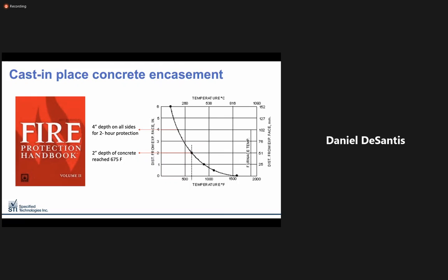This graph here, published by the NFPA in 2008, shows the temperature performance of cast-in-place concrete. This test was performed using an ASTM E119 time temperature curve for a typical cellulosic fire. As you'll see noted here, the unexposed side of 2-inch thick concrete reached 675 degrees Fahrenheit after just 2 hours, while 4 inches were required to maintain a passable temperature of about 325 degrees above ambient, or 400 degrees total.